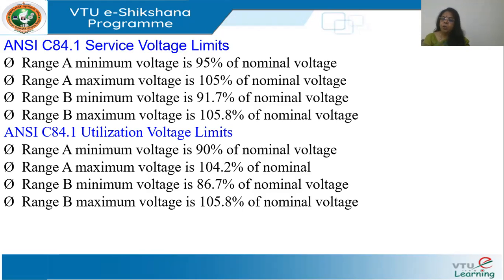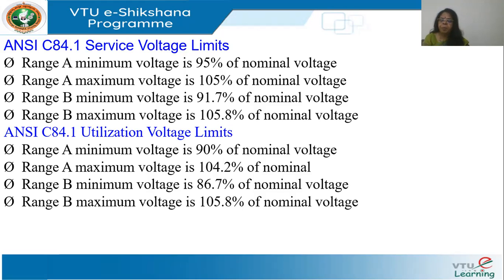The utilization voltage limit is on the customer side, which is further downstream. Larger deviations are possible there. For range A (optimal), it is between 90% to 104.2%, and for range B, 86.7% to 105.8%. These are the ANSI C84.1 standards.